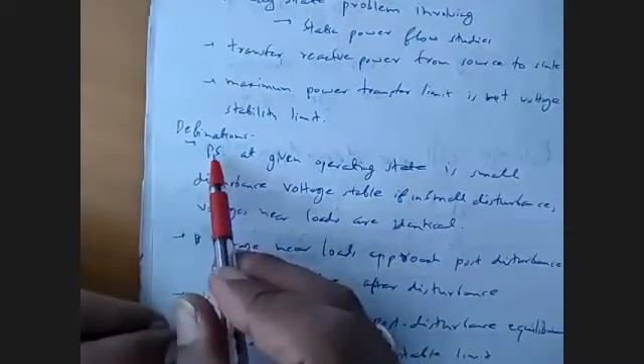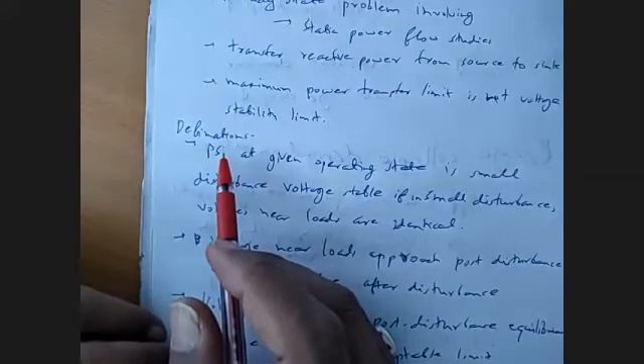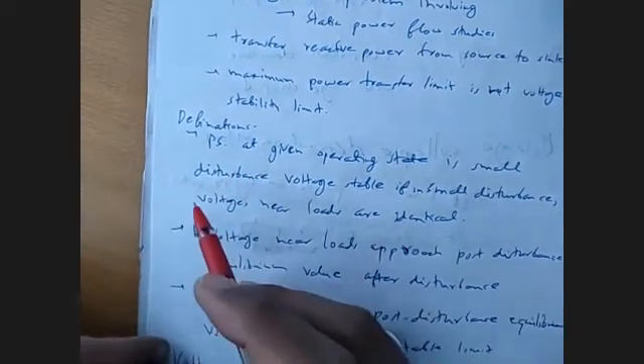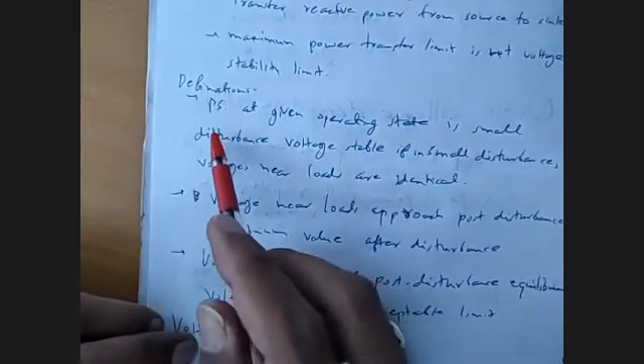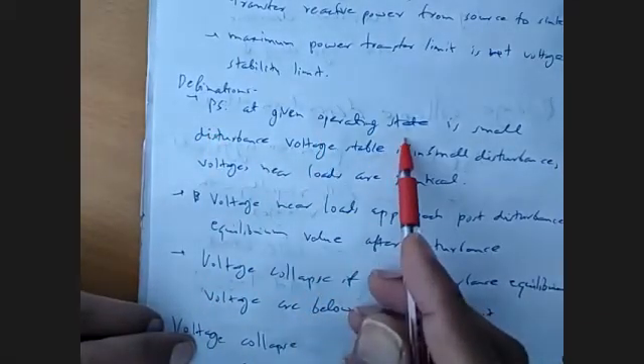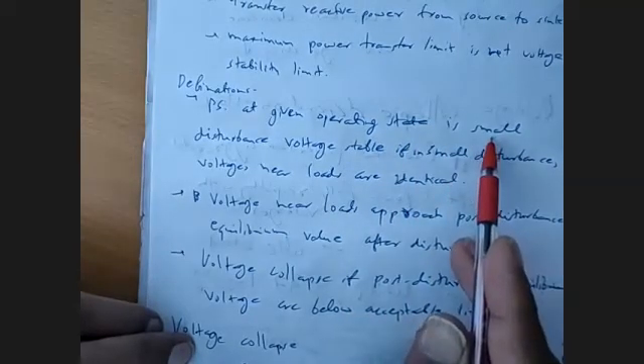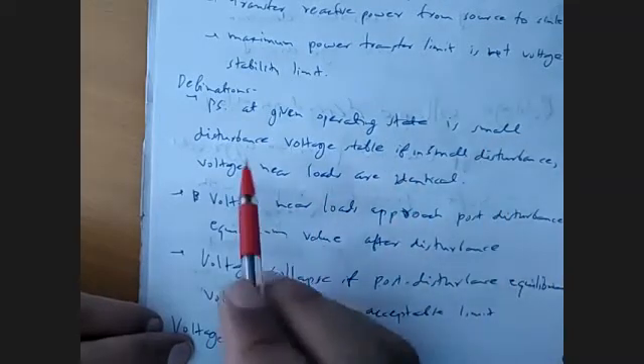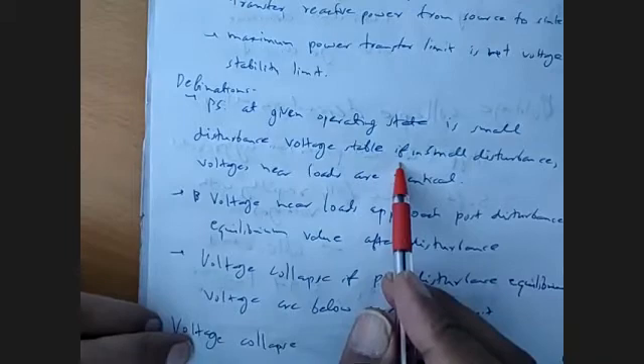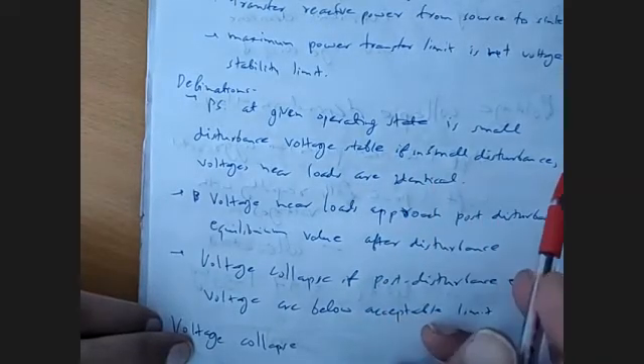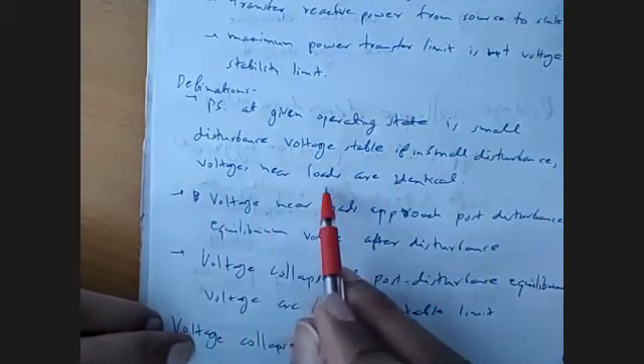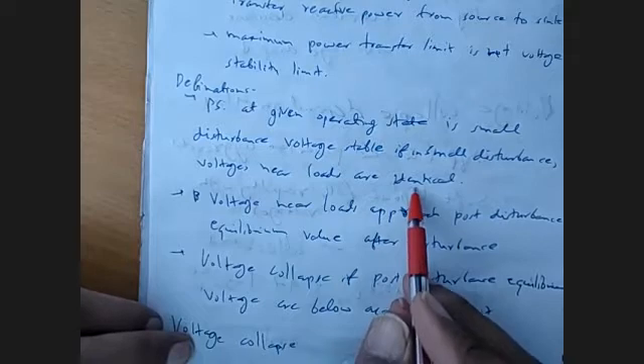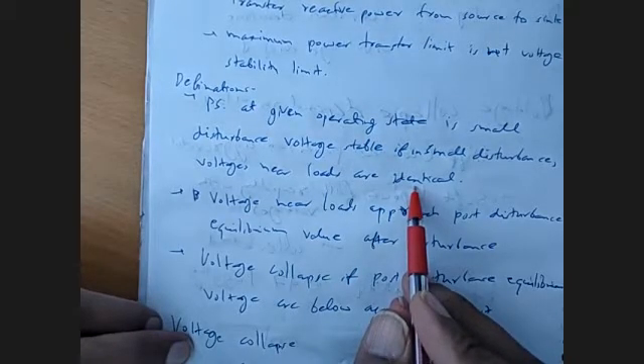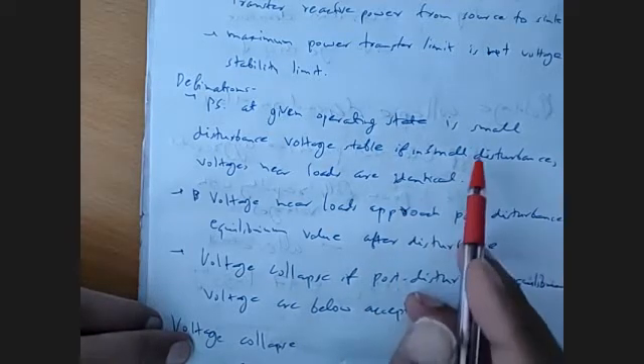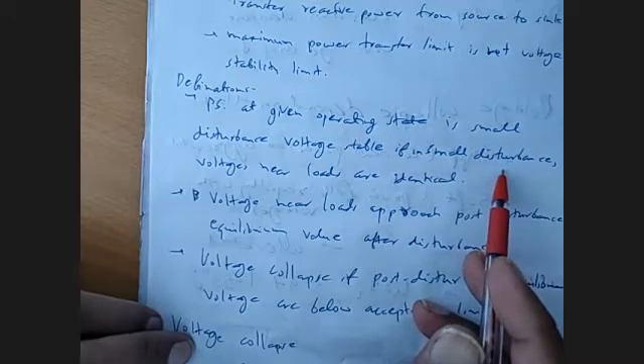So when we are defining power system stability, there are a lot of definitions. Some of them I have discussed or identified. One is that a power system at a given operating state, when a small disturbance occurs in the system, will be voltage stable if, for a small disturbance in the system, the voltage near the load will be identical. That means the voltage is not changed across the load terminals. Then for a small disturbance, that power system is said to be voltage stable.